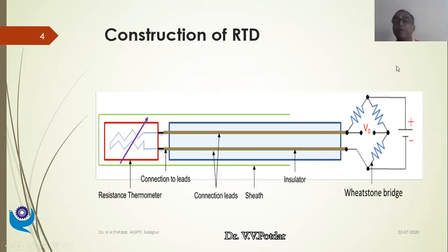How does the control system come to know the present value of the temperature inside the furnace? Through this RTD. This will send the controller a signal corresponding to different temperature values in terms of current values or voltage values. These voltages corresponding to a particular temperature are compared with the set value of the furnace temperature, and accordingly, if the furnace is required to be at 1000 degrees Celsius and the temperature sensed by this RTD is 900 degrees Celsius, I have an error of plus 100 degrees Celsius.